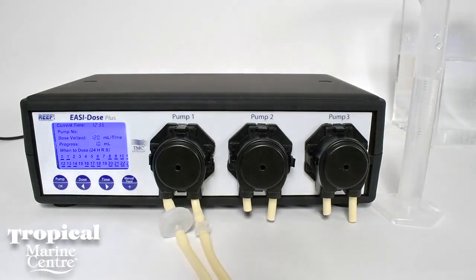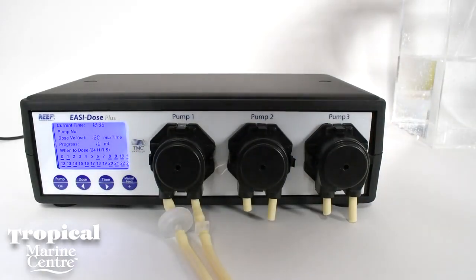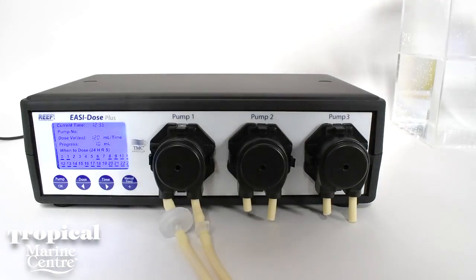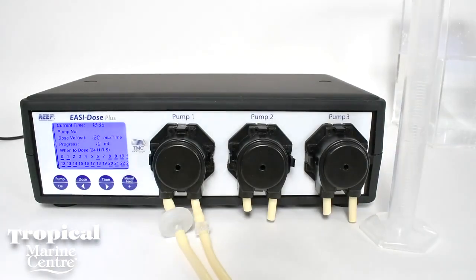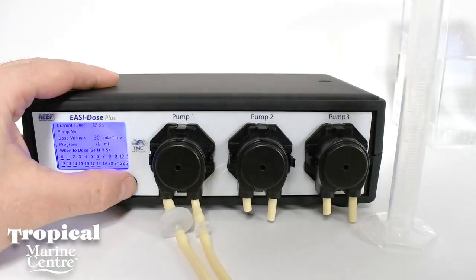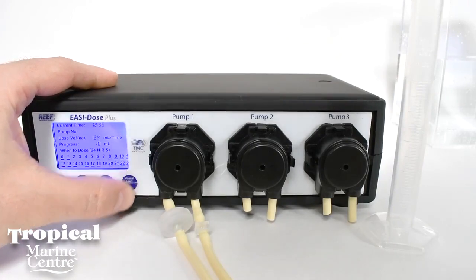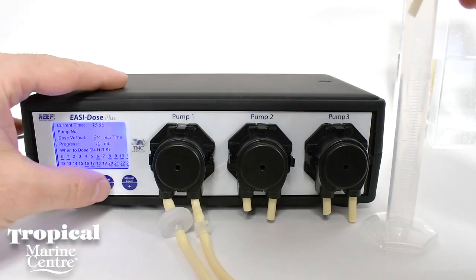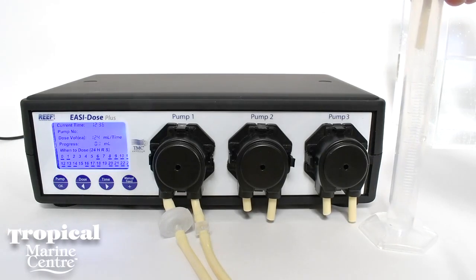To increase the amount, we need to press the manual feed plus button. To decrease, you press the dose left button. You'll see that the dosage volume will increase. We'll set this to 124 to see what happens. Put the tube back into the measuring cylinder and press time again. Now we can see it filling, and we will see whether we have got accurately 10ml or not.